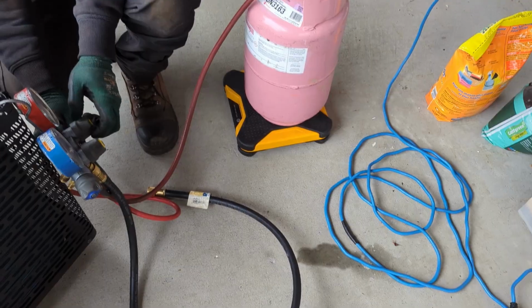So Trevor's like, you can't import a unit with refrigerant in it. What are the chances they've got nitrogen in here just to hold the charge? So we check it out, and sure enough, it was nitrogen in there. There was no refrigerant. So we pulled all the nitrogen out, vacuumed her down, and charged her up with the proper 410A refrigerant.